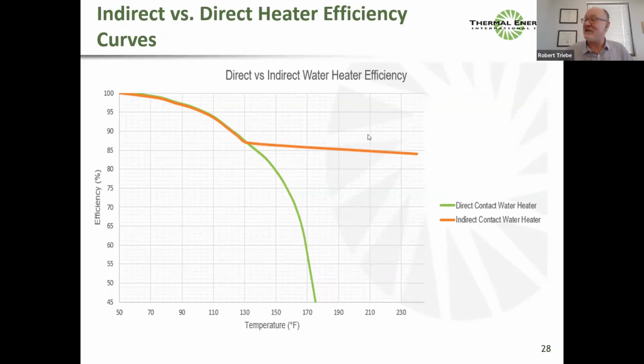I want to spend a little bit of time on this heat recovery curve. So this orange part, this indirect contact water heater curve, that's the same curve we've looked at a few different times. That shows that as you cool the exhaust gas, it shows what your efficiency is. So this is an efficiency curve showing if my exhaust gas from an indirect contact heater is 210, then my efficiency is about 85%. The green curve is the efficiency curve for a direct contact water heater. So for a direct contact water heater, I'm going to pick that 160 degree point that my customer had. And so my customer was imagining they were sitting about here, that look at this, I'm at 85, 86% efficiency because I'm going out at 160.